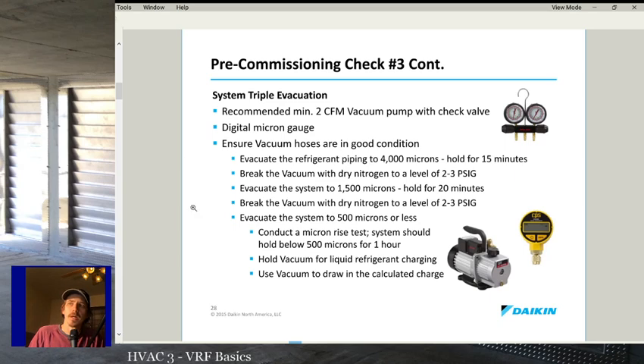So evacuate the piping down to about 4,000 microns. Hold for a few minutes. Make sure it says 15, but hold for a few minutes at about 4,000, and make sure you're not rising all the way back up to atmosphere. If you rise back up to atmosphere, you probably have a leak. You need to leak check again. But if you hold around 4,000 and everything looks good, then you probably don't have a leak. You still might have a really small one, but you probably don't.